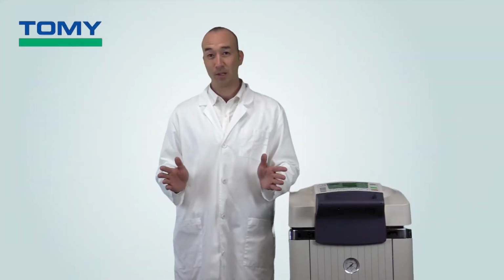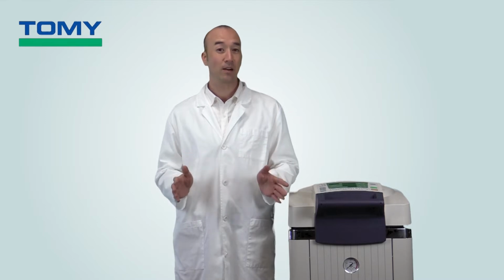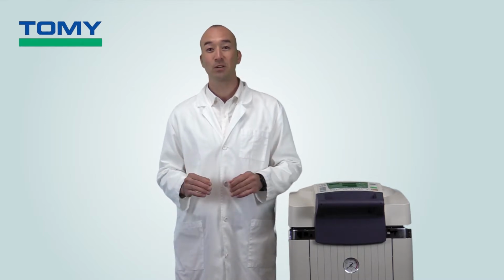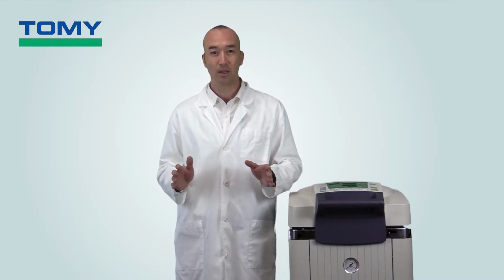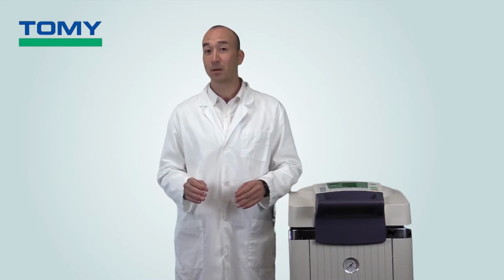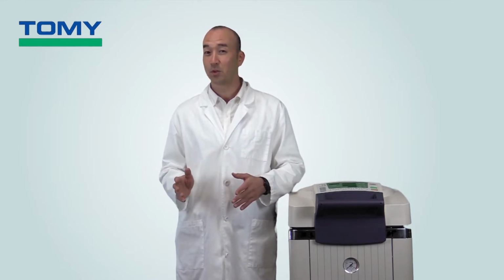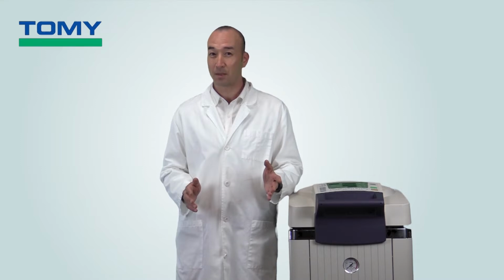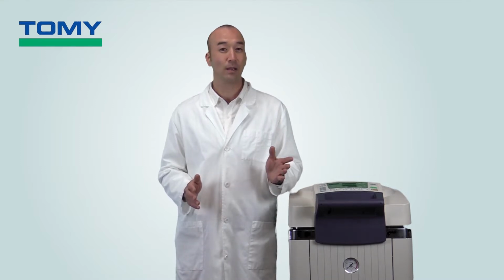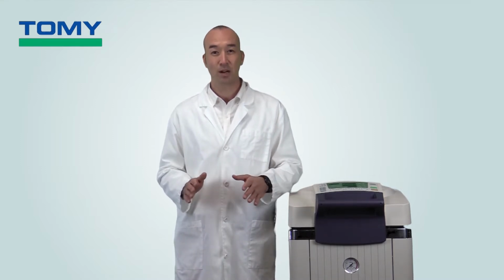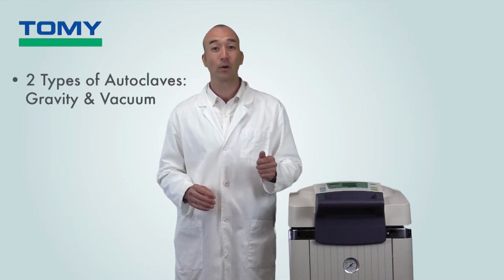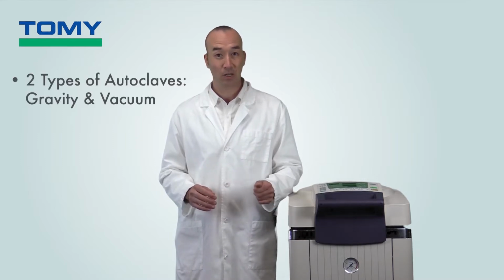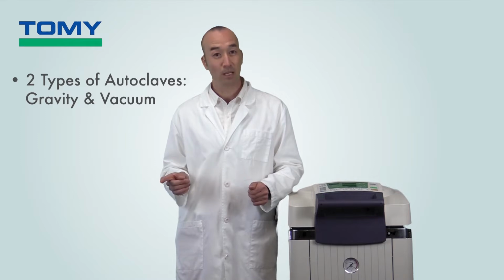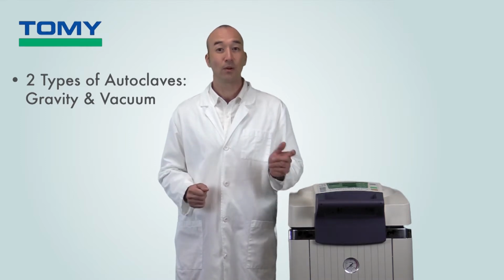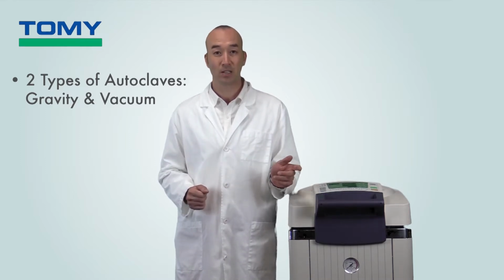You're probably already familiar that an autoclave, or steam sterilizer, functions through the application of highly pressurized saturated steam. You may also know that autoclaves come in a number of different shapes and sizes, but what you may be learning now for the first time is that there are different ways that autoclaves create and maintain heat and pressure. In this video, I'll be going over two main types of steam sterilization: gravity or gravity displacement, and vacuum-induced or pre-vacuum, also known as pre-vac sterilization.